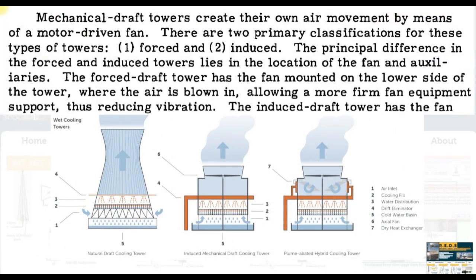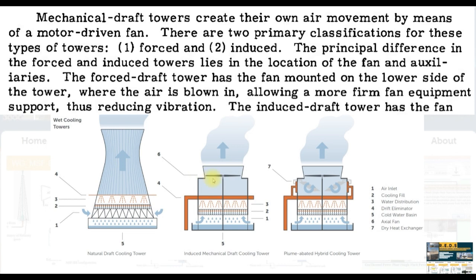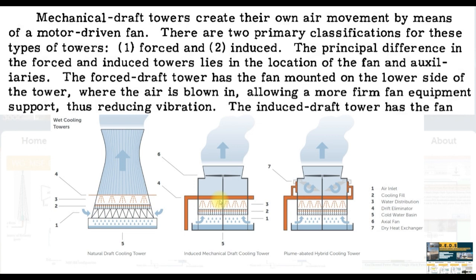Mechanical draft towers create their own air movement by means of motor-driven fans. There are two primary classifications for these types of towers: forced and induced. The principal difference lies in the location of the fan. The forced-draft tower has the fan mounted on the lower side of the tower where air is blown in, allowing more firm fan equipment support, thus reducing vibration. The induced-draft tower has the fan at the top forcing air suction counterflow of the water falling.